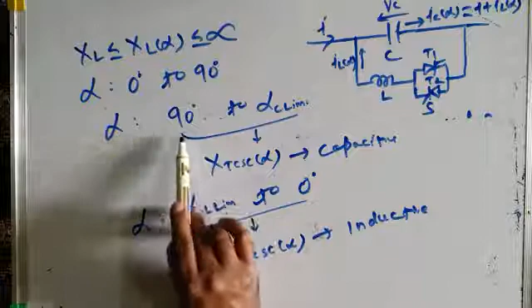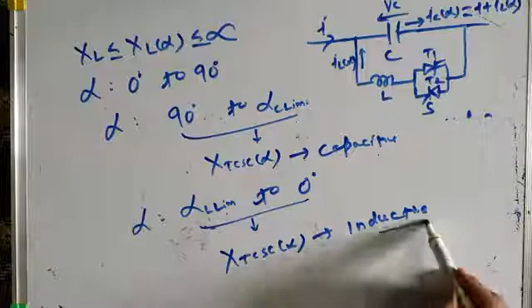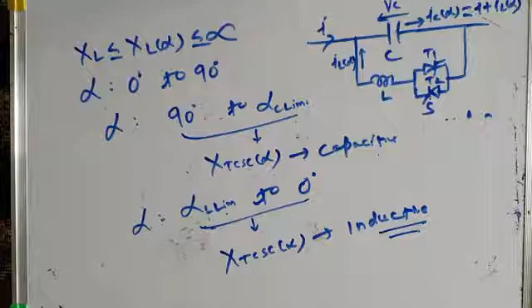So therefore, we can make TCSC behave as a variable capacitive reactance, or as a variable inductive reactance, if we operate it within these two ranges of alpha. If you operate your TCSC in the delay angle range 90 degrees to alpha C lim, then it will behave as a variable capacitive reactance. And if you operate it in the delay angle range alpha L lim to 0 degree, it will operate as a variable inductive reactance, the inductive region. So hence we can make it operate as a variable capacitance or as a variable inductance depending upon the delay angle range. Okay.